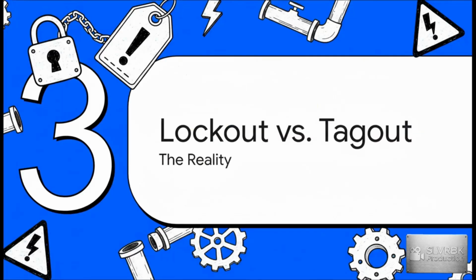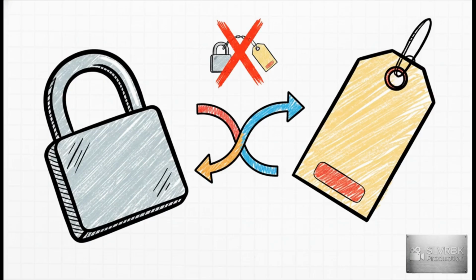Section 3. Lockout versus tagout reality. Let's clear some things up. We need to dismantle one of the most misrepresented concepts in the industry right now. The biggest myth out there is that a tag must be placed with a lock every single time a lock is applied. That's actually false. Now sure, a lot of employers simply bake that rule right into their company policy, and hey, that is totally fine. Like we just talked about, you can always make rules stricter.